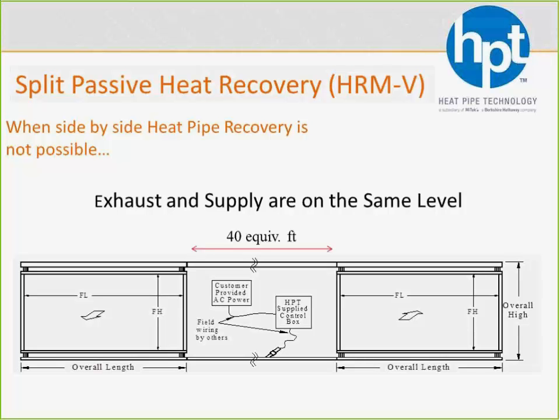When we have these headers, now the circuits are within tubes that are running vertically within the heat pipes to go from header to header, and it's those vertical tubes that give the HRM-V its model name. The V is for the vertical tubes. Now we do have some limitations. Again, we still don't need pumps, but that means we can only run so far before the refrigerant's just going to stop moving. The head is only going to push it so far.